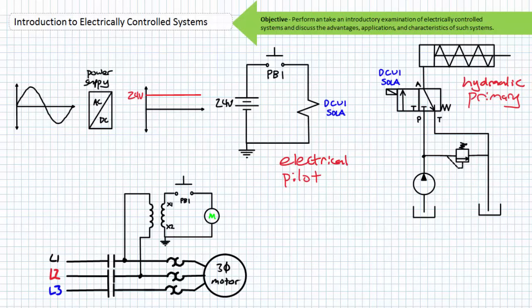One being the primary hydraulic schematic, the other being the electrical pilot schematic. In this simple example, there exists a single interaction point between the two aspects of the system, that being solenoid A on directional control valve 1. When push button 1 is closed in the electrical schematic, DCV1 solenoid A is energized. On the hydraulic schematic, the energized solenoid A would shift DCV1 to the straight-through position and the cylinder would extend.